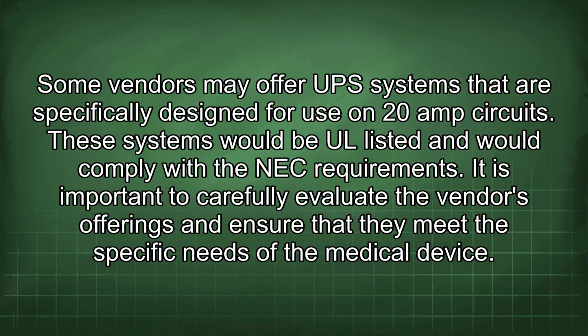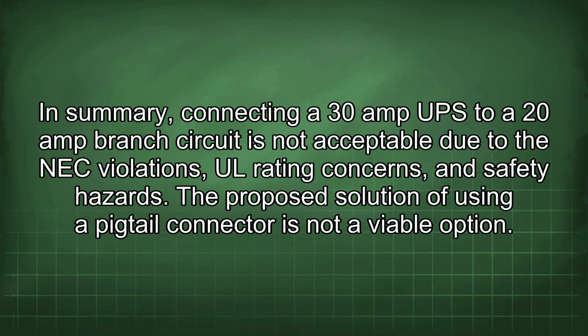Some vendors may offer UPS systems that are specifically designed for use on 20 amp circuits. These systems would be UL listed and would comply with the NEC requirements. It is important to carefully evaluate the vendor's offerings and ensure that they meet the specific needs of the medical device. In summary, connecting a 30 amp UPS to a 20 amp branch circuit is not acceptable due to the NEC violations, UL rating concerns, and safety hazards.